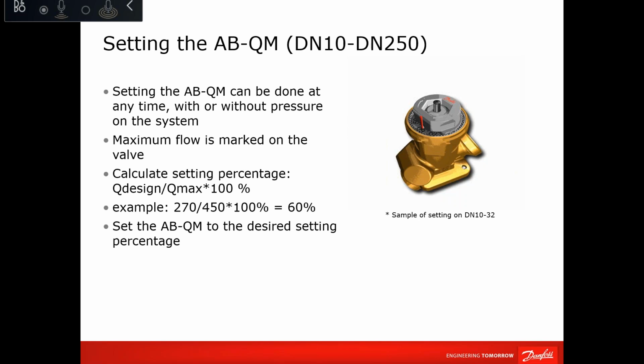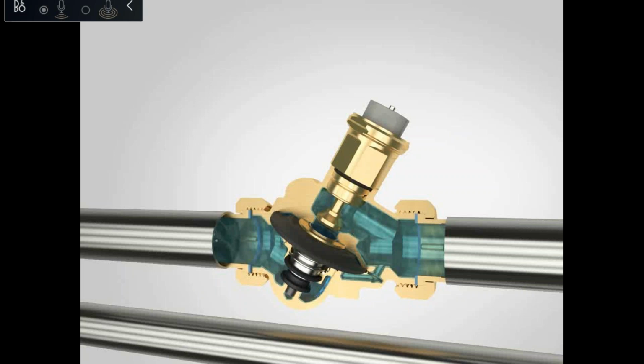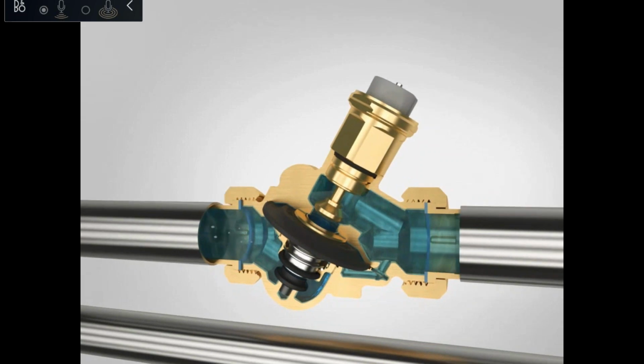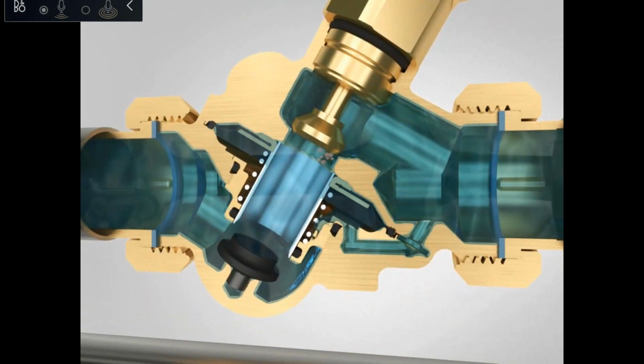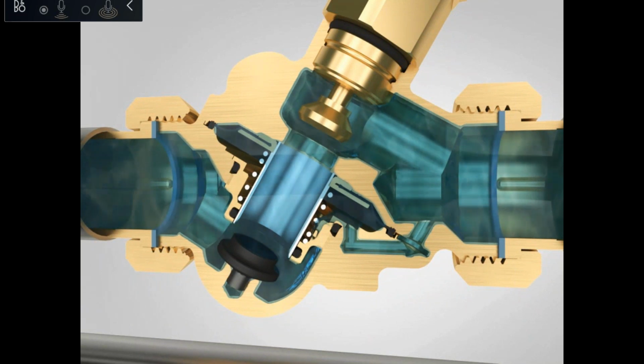Now we spoke about it, it's a bit complicated internally, but now in the next slide, you will see that it is really not complicated at all, because with multiple parts in PICVs, one to control the flow, one to maintain the flow, and two valves combined together, test port, membrane, disk, etc., there would be a risk of blockage. In order for us to remove that risk completely, the valve design itself is like an S-trap. So if you can see in this animation, the cone and the seat of the pressure controller part is a cylinder. It's an open cylinder from the inside, which means if you take this cut piece, the valve is only an opening, or it's a tube, let's say it's a pipe.